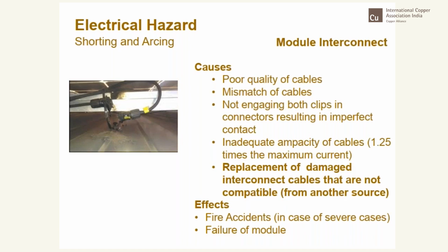Then we have the module interconnects. Nowadays we have male-female connectors, and if the cables are not of good quality... Many times, if a particular cable has gone bad, we try to replace it, and unfortunately we don't have a very good standard. The connectors provided by one company are not compatible with those supplied by another, so there could be loose contact arising out of that, and that could be a potential source of fire.